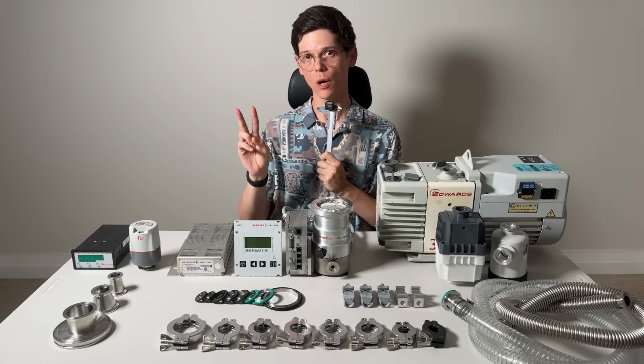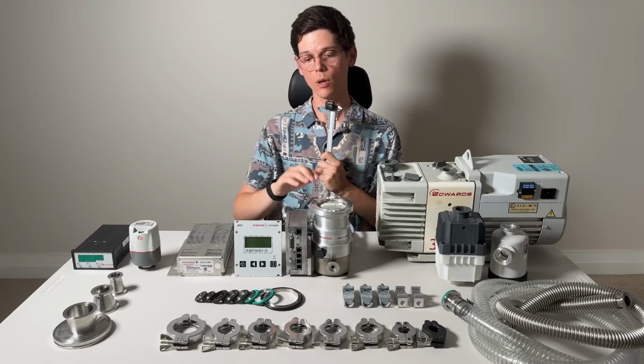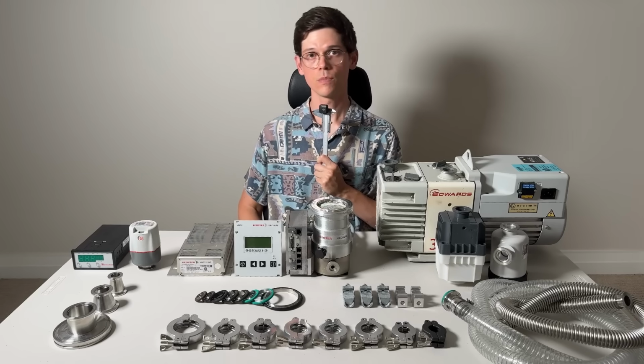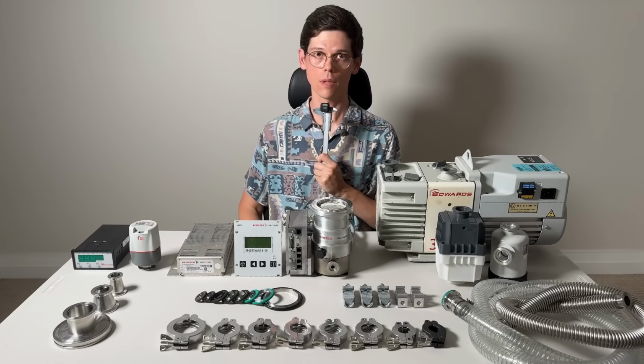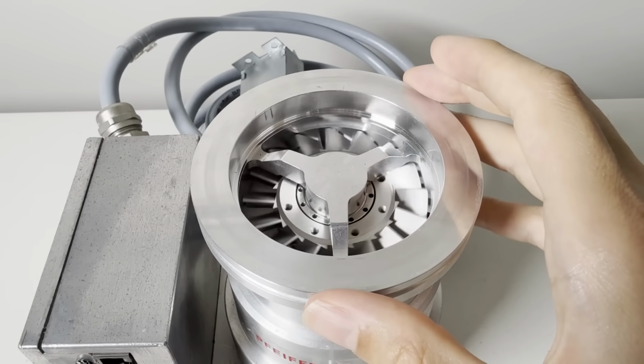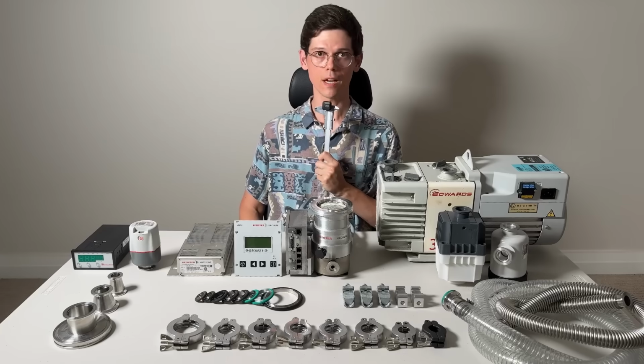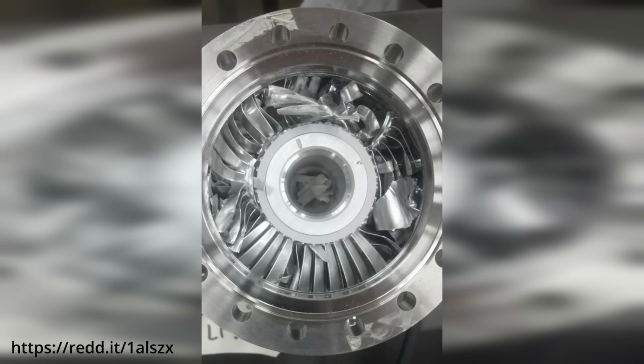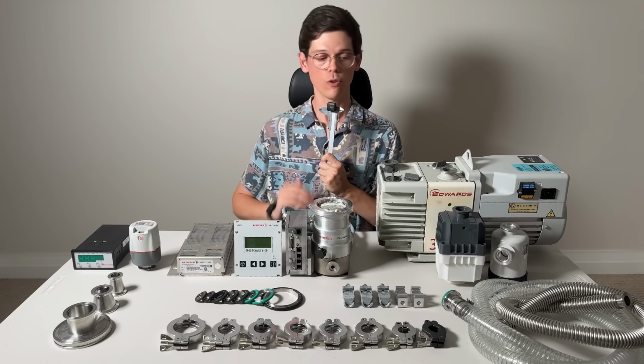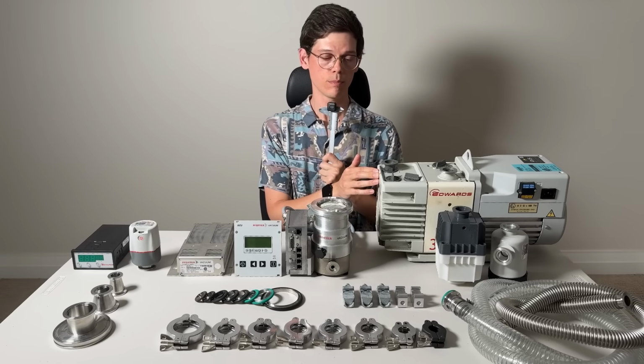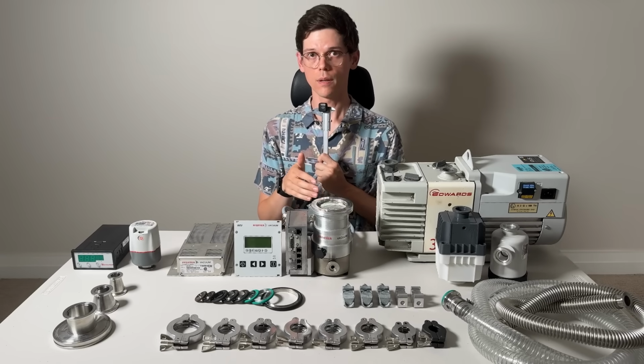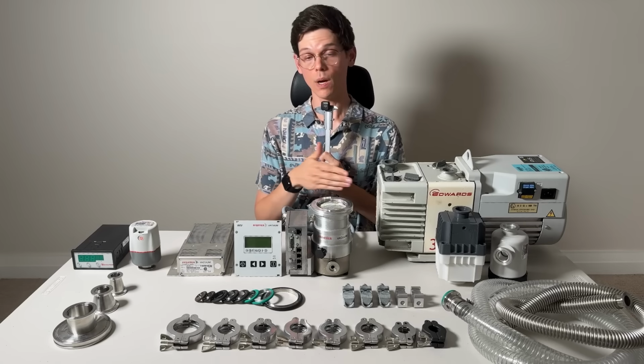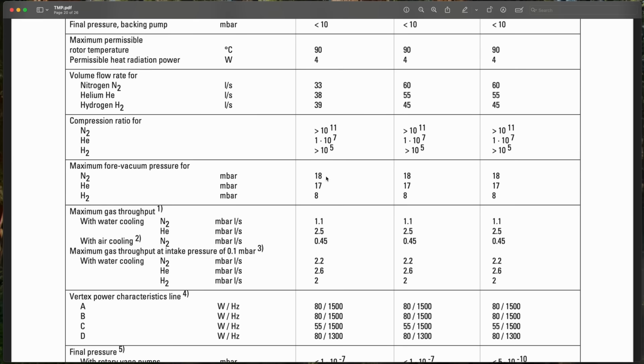There are 2 important things to note though. The first is that the turbo has a maximum operating pressure. If you try to run it at too high of a pressure, like atmospheric pressure, that can be a bit too much for the blades inside, and when they're spinning at 90,000 RPM, that's not going to be a good time. To avoid that, you first run a roughing pump, like this one, until you reach the turbo's operating pressure, and only then do you turn it on. That's why I need 2 pumps. This turbo's operating pressure is 18 millibar, which is well within the capabilities of this pump, so we should be fine.